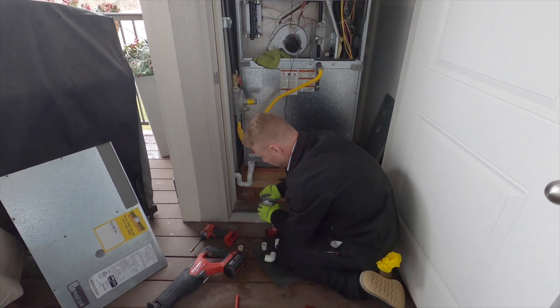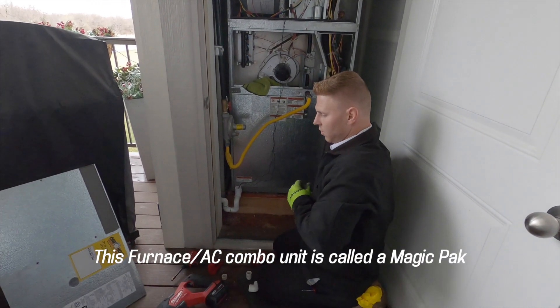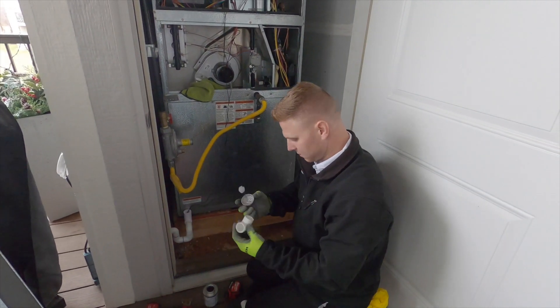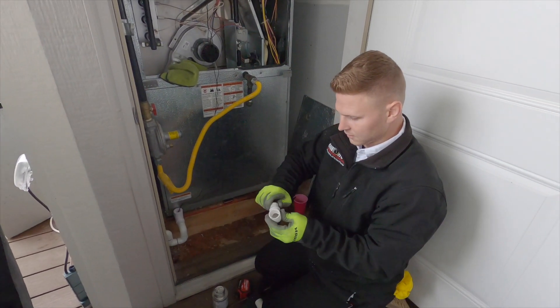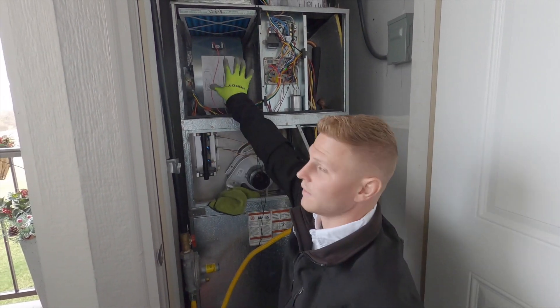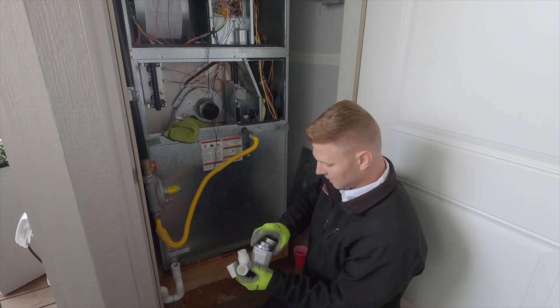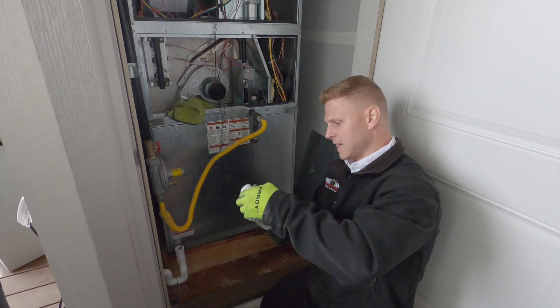Are these units completely separated or are they attached to their neighbors? No, they're completely separated — the vents just go in the edge of the house and around. Yeah, they're all independent package units, which is kind of nice. They're different to work on than what we usually do because we're pretty much split units most of the time — condenser outside, evaporator coil inside with the furnace underneath. This is your evaporator coil, this is your condenser, this is your furnace, and that's your blower motor. On normal units this is all split into two, so what's cool with these is it's a great learning experience to see how everything works and interacts in one spot.